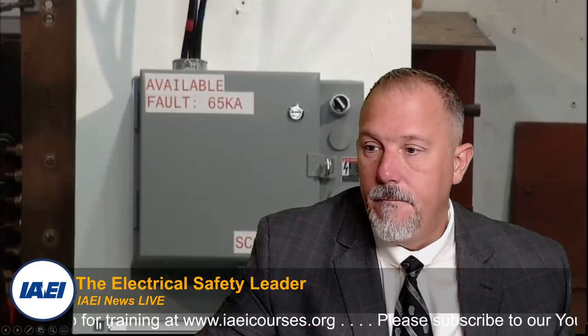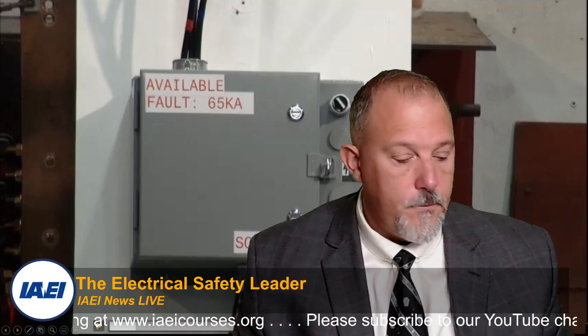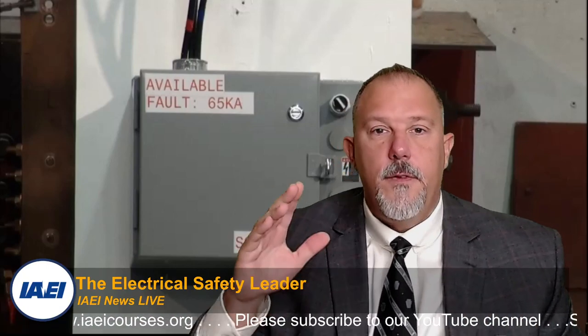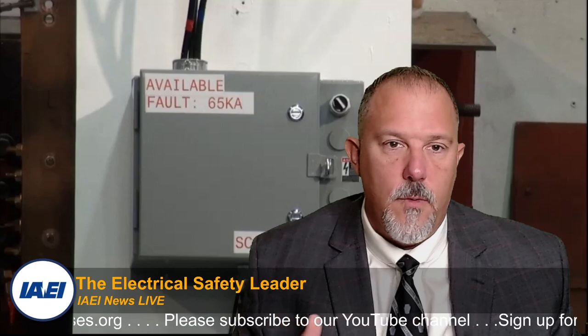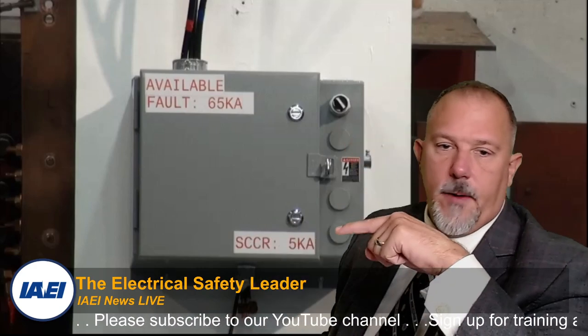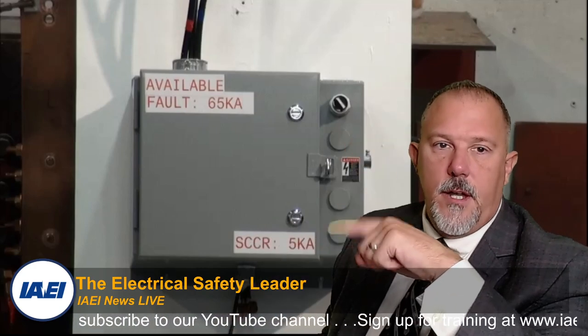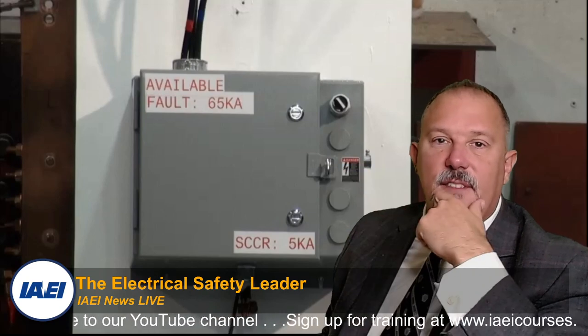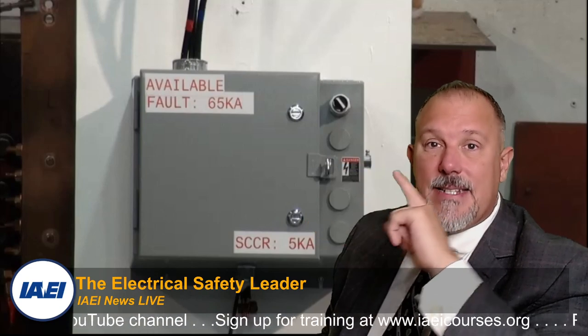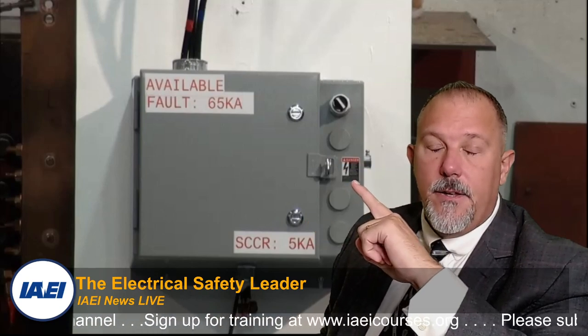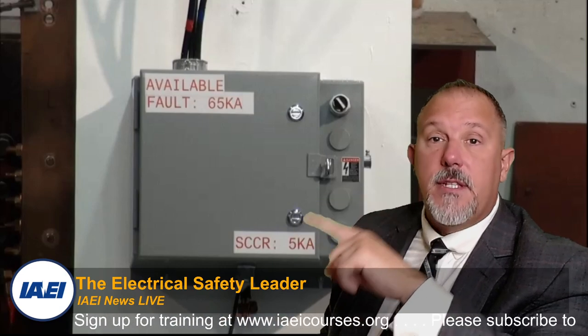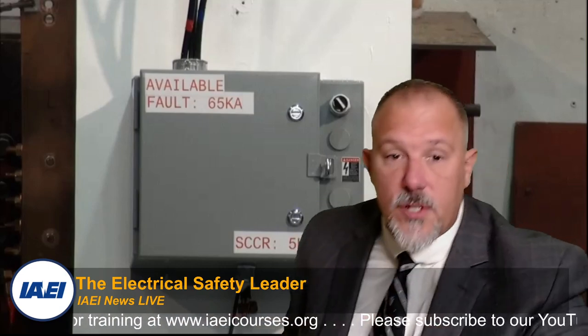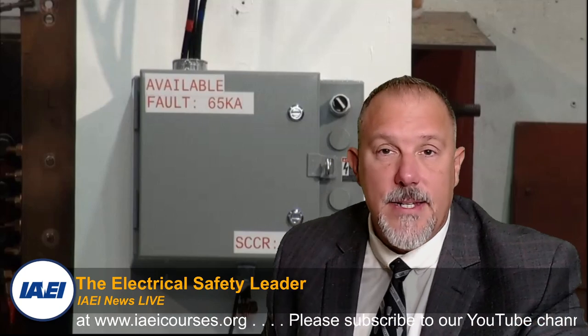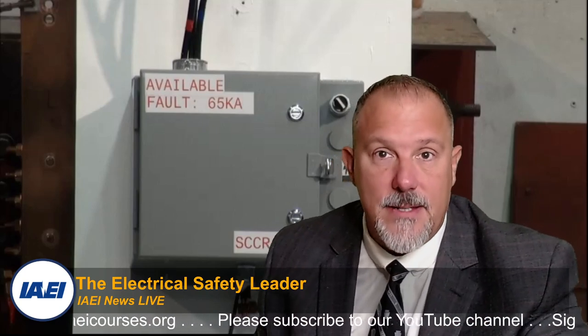Now, before I play this one, this video does a couple things. One, look at the short circuit current rating. It's 5,000 amps. The available fault current is 65,000 amps. I am exceeding the short circuit current rating of this equipment. You know what's going to happen. I'm going to achieve an unintended rapid disassembly in the field.